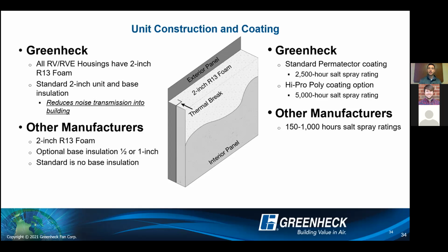So we standardly inject that R13 foam in the base as well as the unit. So what's nice about the base is it reduces both noise transmission into the building as well as some additional thermal resistance that you're going to lose, especially if you have an uninsulated curb, maybe it's pad mounted, things like that.